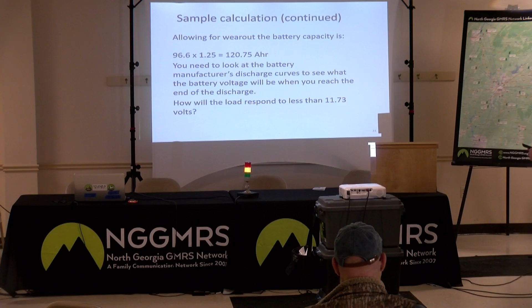A lot of batteries have a limit on charging current. And it varies according to the battery by manufacturer. And even within a manufacturer, it may depend on which of the batteries they offer. They offer one battery that'll have a different limit than some other battery. A lot of lead acid batteries, you can recharge them up to about 1/4 of their ampere hour rating. So a 100 ampere hour battery, you can charge it at about a 25 ampere rate.